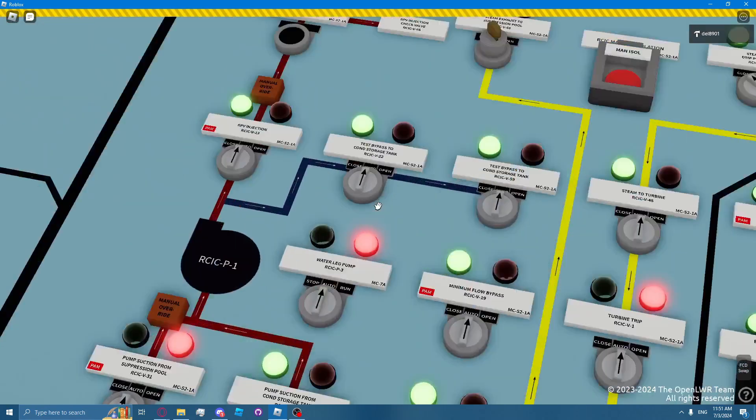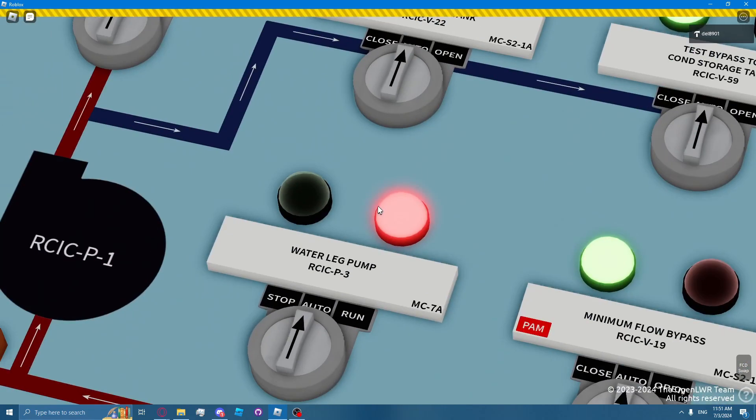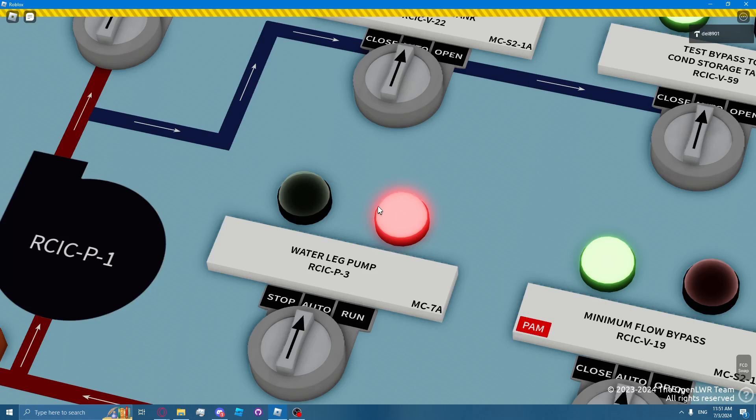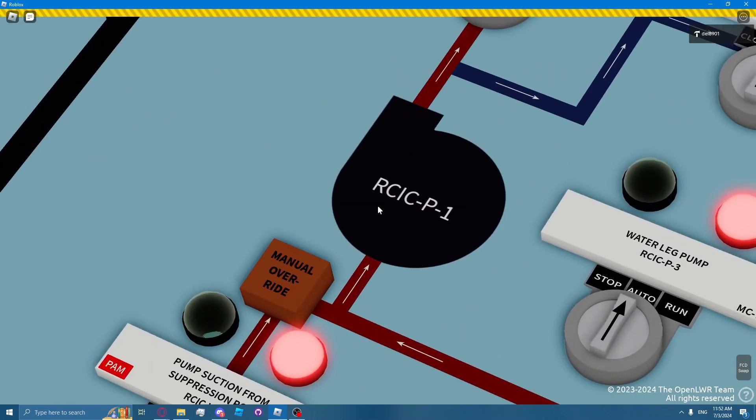The RCIC water-leg pump, RCIC P3, discharges to the RCIC discharge line to ensure it's full of water, which prevents water hammer in the line when the RCIC system is initiating. The RCIC pump, RCIC P1, is a centrifugal pump which delivers around 600 gallons per minute of water to the reactor.